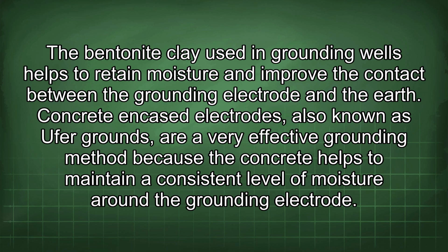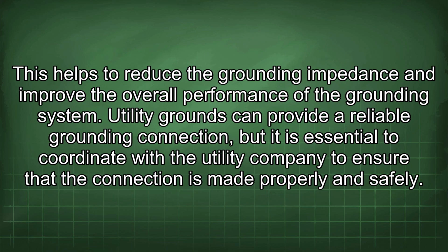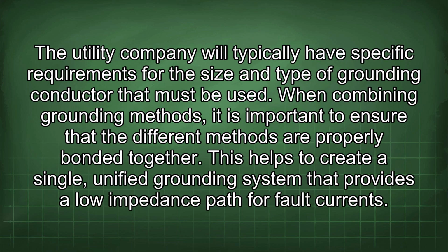Concrete encased electrodes, also known as Ufer grounds, are a very effective grounding method because the concrete helps to maintain a consistent level of moisture around the grounding electrode. This helps to reduce the grounding impedance and improve the overall performance of the grounding system. Utility grounds can provide a reliable grounding connection, but it is essential to coordinate with the utility company to ensure that the connection is made properly and safely. The utility company will typically have specific requirements for the size and type of grounding conductor that must be used.